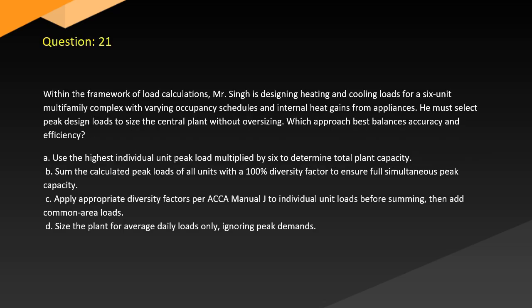Question 21. Within the framework of load calculations, Mr. Singh is designing heating and cooling loads for a 6-unit multifamily complex with varying occupancy schedules and internal heat gains from appliances. He must select peak design loads to size the central plant without oversizing. Which approach best balances accuracy and efficiency?